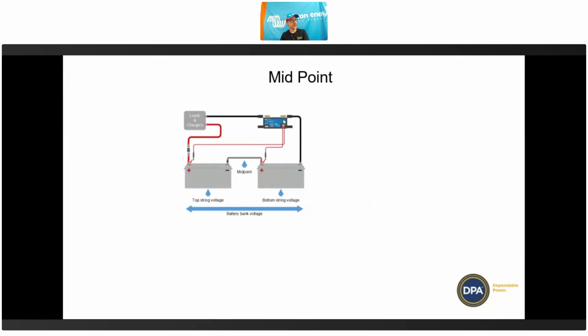That's an example of what midpoint wiring looks like. You've got two 12-volt batteries in series, and you've got the shunt wired on the negative like we described before, and then you've got one positive going to the main positive connection, and then you've got the second one going at the midpoint in between the two batteries that are in series. What it's checking is that both of the 12-volt batteries are exactly the same voltage. Say if the total voltage is 24, we'd want both of them to be exactly 12.